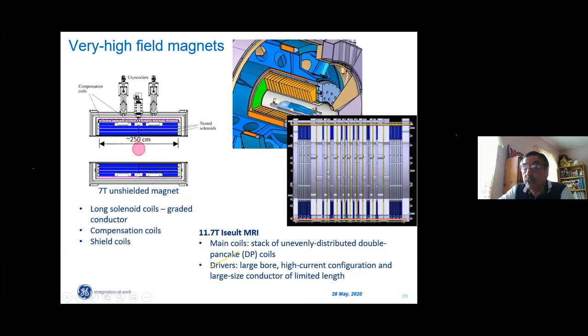The Iseult magnet used a completely different technology because of extremely high stored energy, 350 megajoules or so. They had to operate at very high currents, and layer wound appeared to be not the best technology. So their main coils are pancake wound, and each pancake coil must be installed at a very specific position. This is probably the right decision for the ultra-high field 11.7 Tesla magnet, but it is not advantageous for commercial price-driven systems. But I try to show how different technologies may work here.